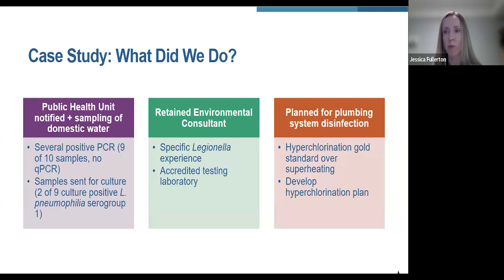With our consultant and the help of our local public health unit and Public Health Ontario, we determined that we really did need to disinfect our entire plumbing system, to, I won't say eradicate, but to really minimize the concentrations of Legionella in our system. Hyperchlorination is considered the gold standard for disinfection, although superheating can be used in instances where hyperchlorination may not be appropriate. And then we were putting together our hyperchlorination plan, and that was certainly no easy feat. That took several days of coordination to put together a plan on how we were actually going to implement this.